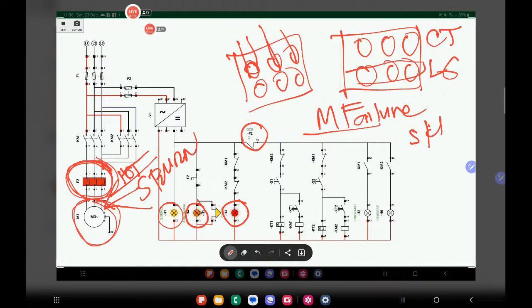I think because it is also always being used, right? Every time your main contactor is running, right? So this F2 will also be a possible cause why you're having an overload alarm. The overload relay itself is the problem.